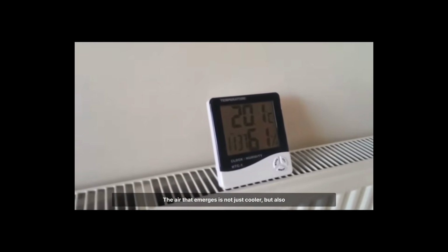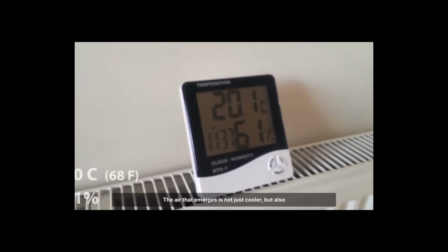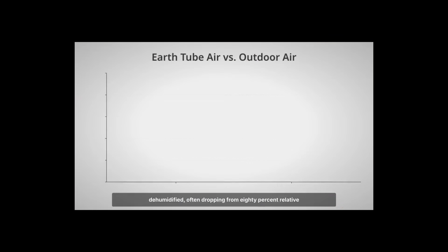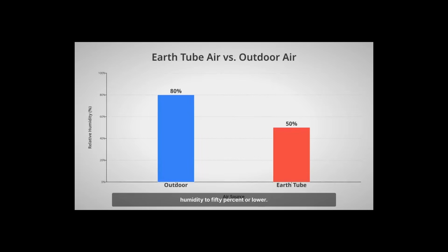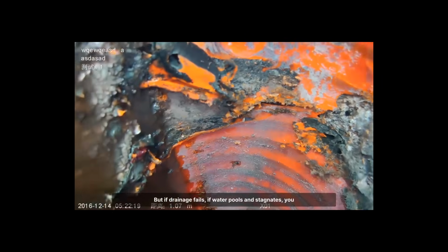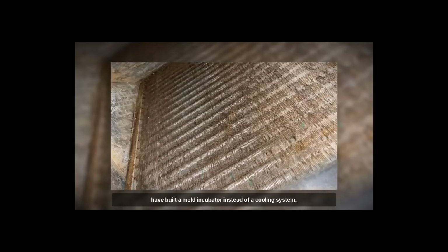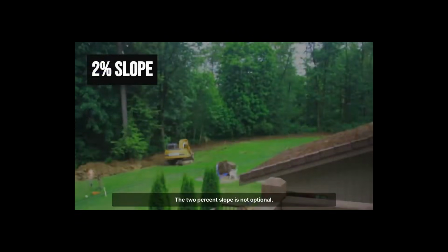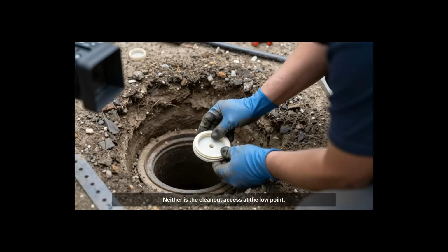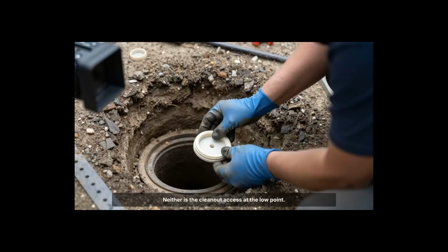The air that emerges is not just cooler but also dehumidified, often dropping from 80% relative humidity to 50% or lower. But if drainage fails, if water pools and stagnates, you have built a mold incubator instead of a cooling system. The 2% slope is not optional. Neither is the cleanout access at the low point.